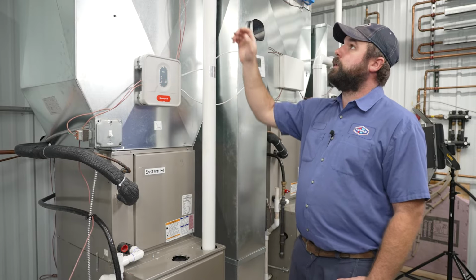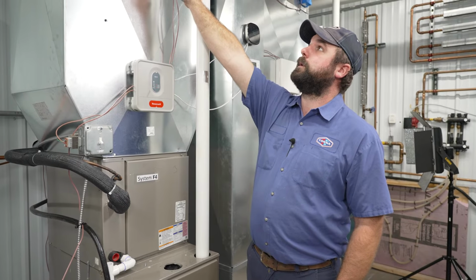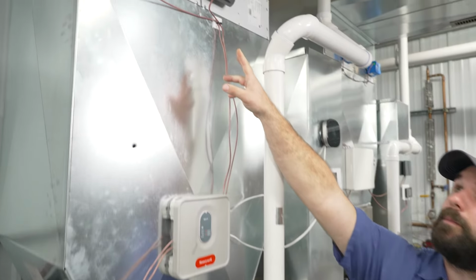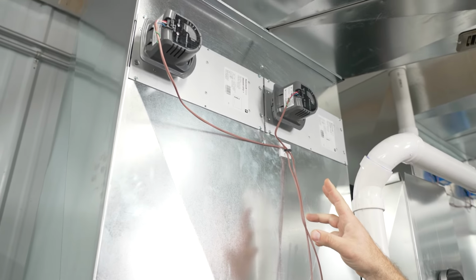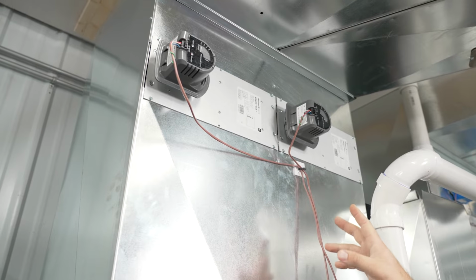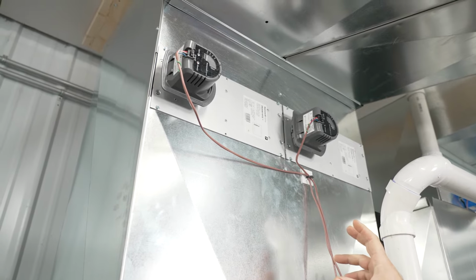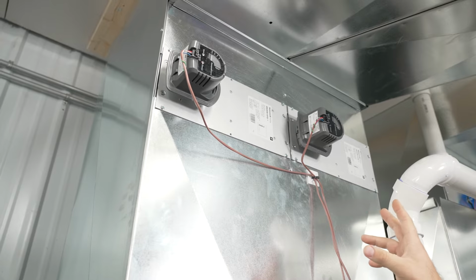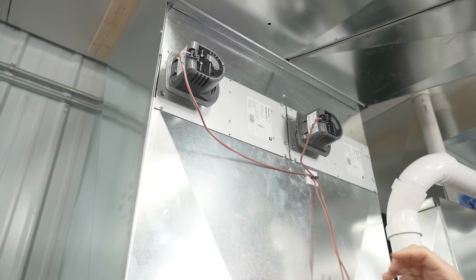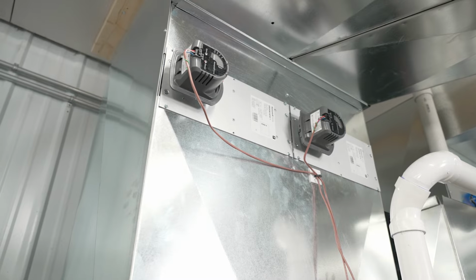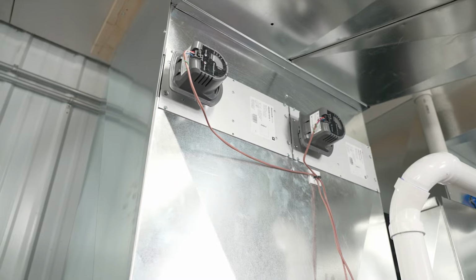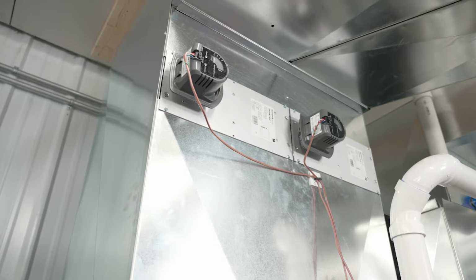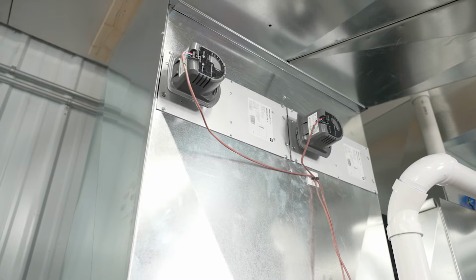And then also up here, you have, in some houses, zone dampers. These just control the flow of air according to if you have several different thermostats in the house. We make sure they're functioning properly, which we will check during the base of the maintenance. Sometimes they can get stuck and we want to make sure they're free and clear and working properly too.